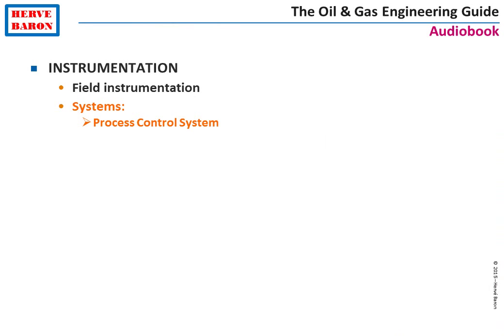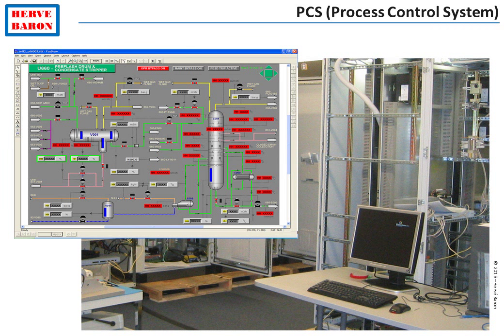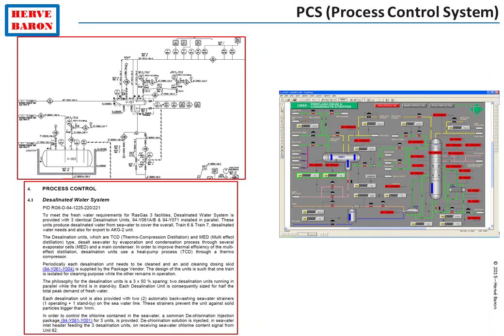Another work stream of this discipline is the systems. First of all, the process control system. Its functionalities are entirely defined by process, by means of two documents: the P&IDs, which show the process controllers and all instruments that are part of the process control system, as well as control narratives or functional analyses, which explain in more detail the control functions that shall be implemented in the process control system.